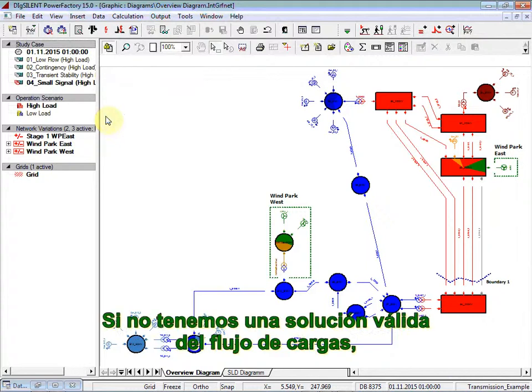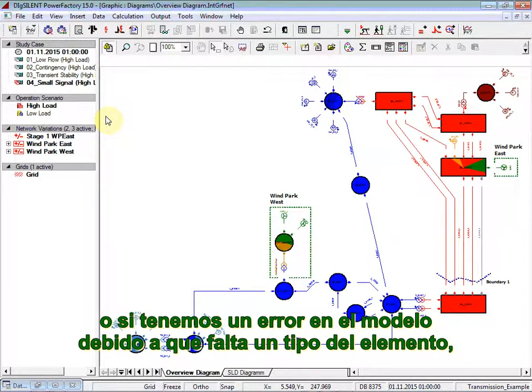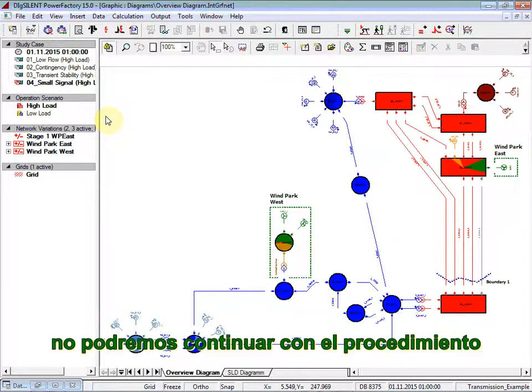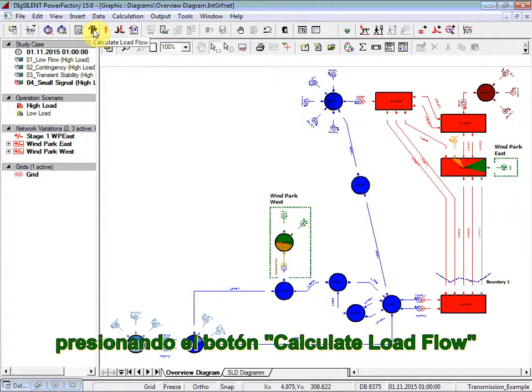If we don't have a valid load flow solution, meaning if we don't have convergence for instance, or if we have a model error because of a missing type of an element, we will not be able to continue with the procedure. So we calculate first a load flow by clicking on the Calculate Load Flow button.